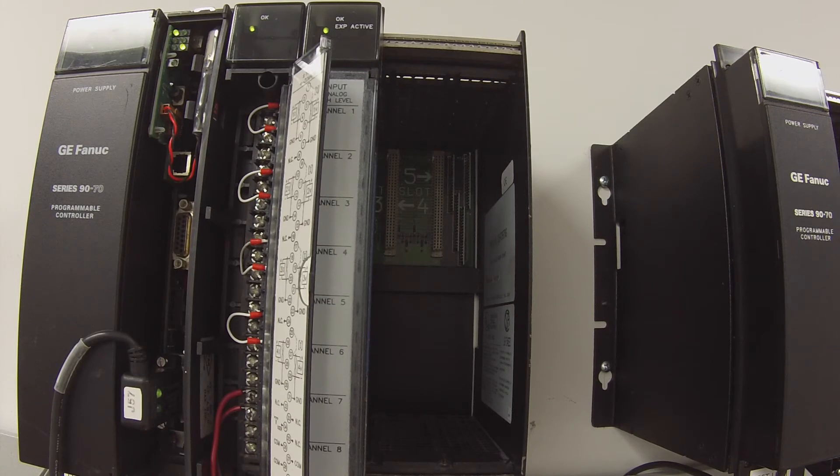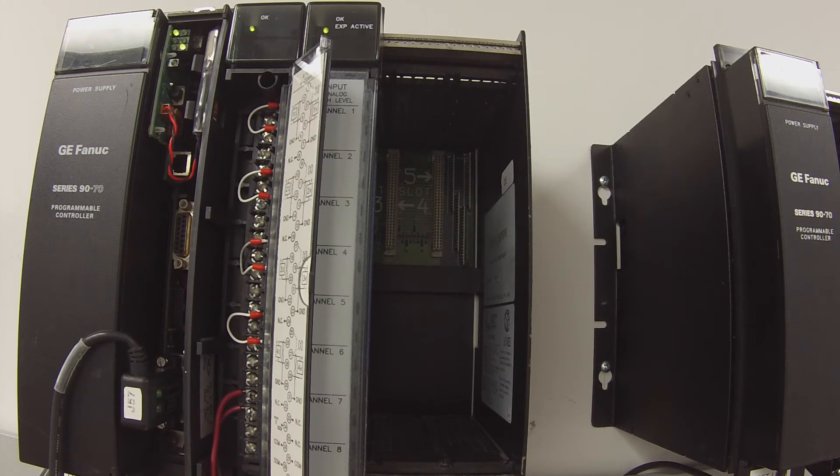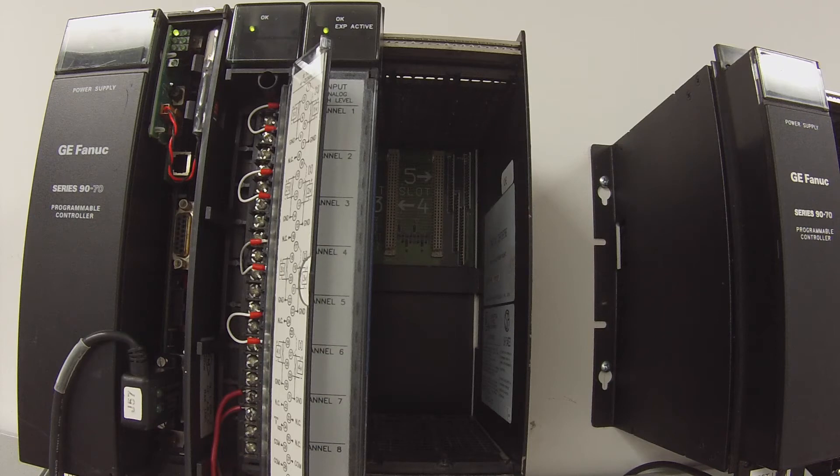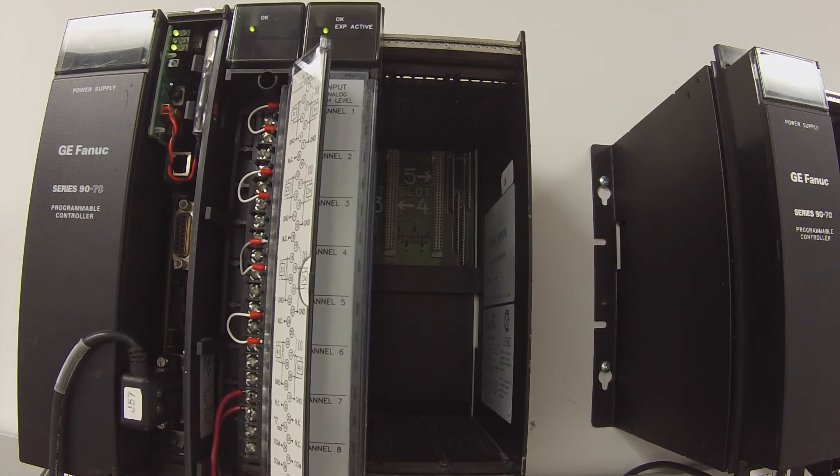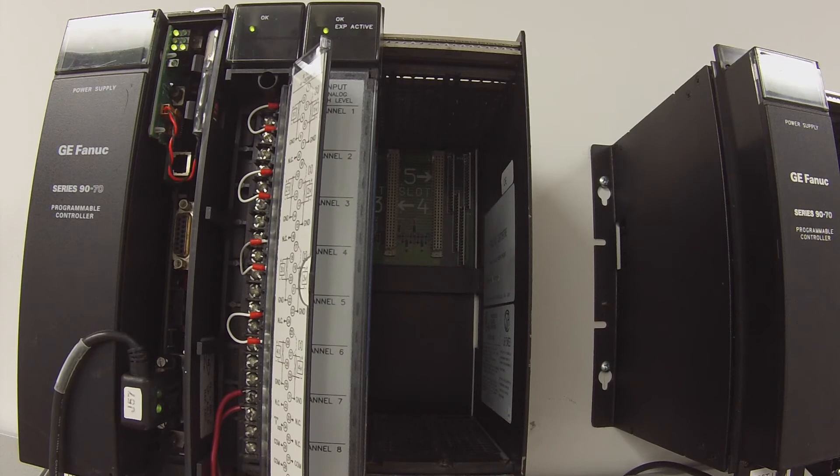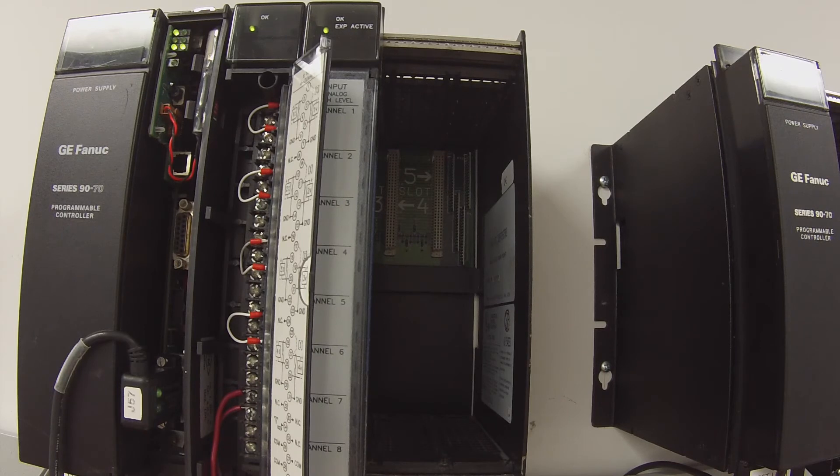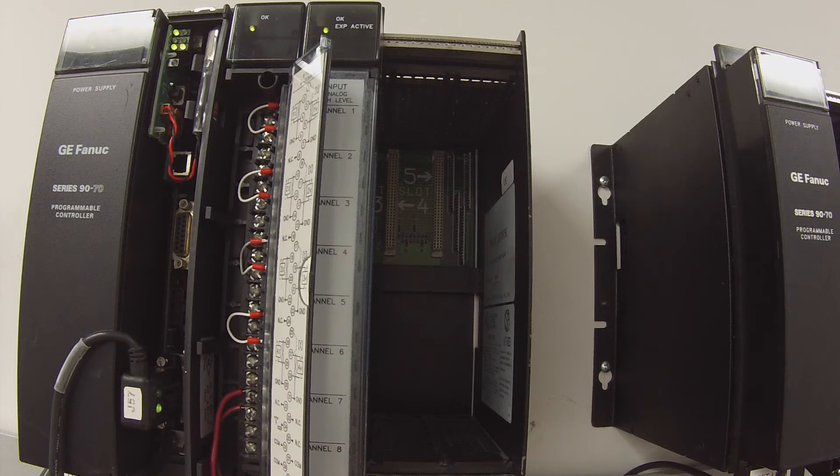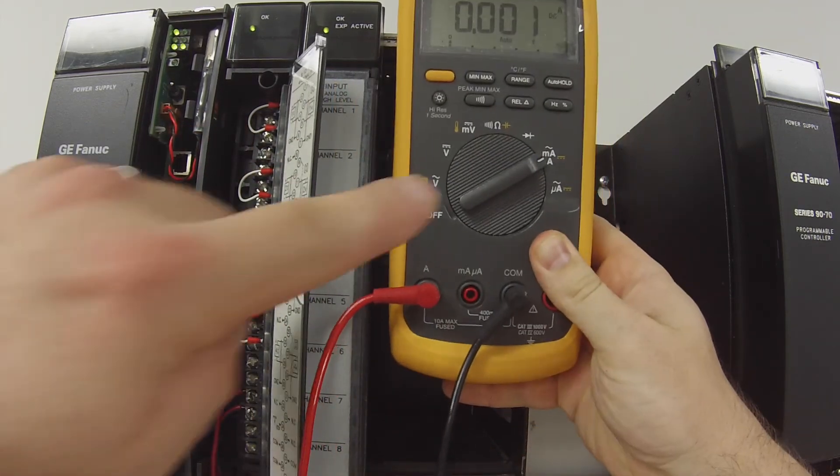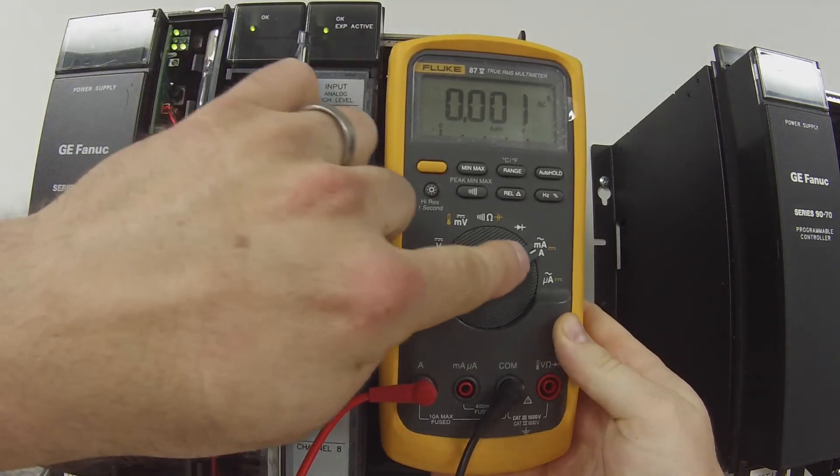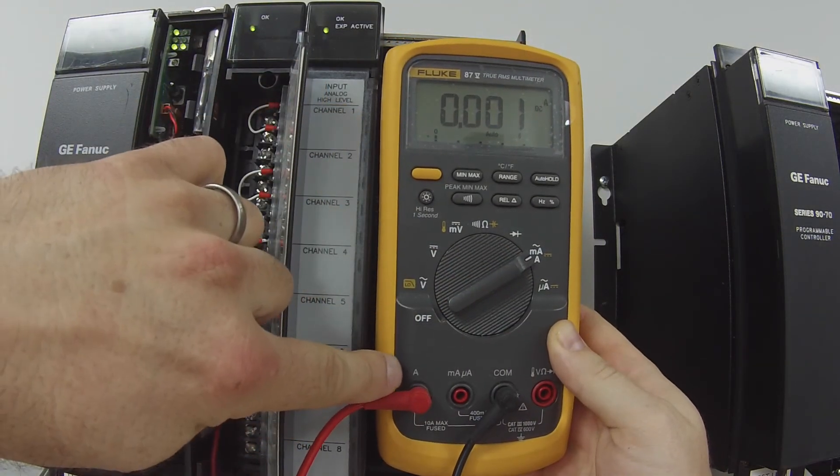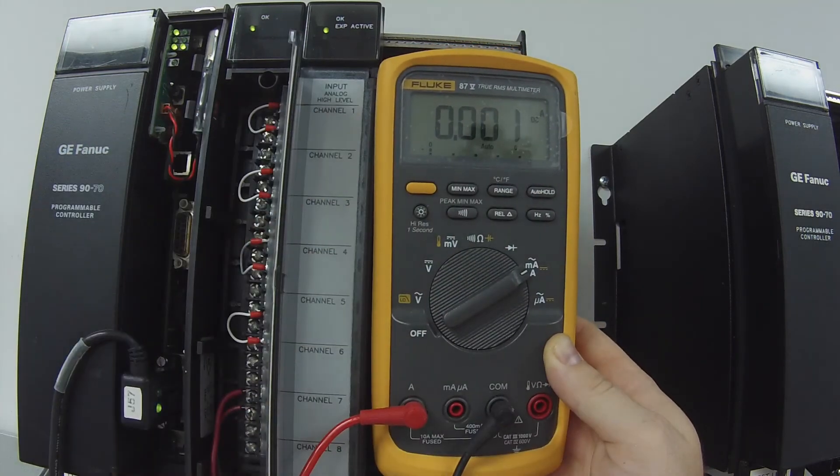Once we're back in run mode, we're going to do the same procedure. We're in run mode. Go back to analog output, put in my values of 32,000 in all four channels. Now I'm going to switch my meter to read milliamps in DC. If you have a meter like this, this selects AC or DC. You want DC. It's set up for milliamp. I have it over to the far left-hand side so I have a more detailed reading, more decimals.